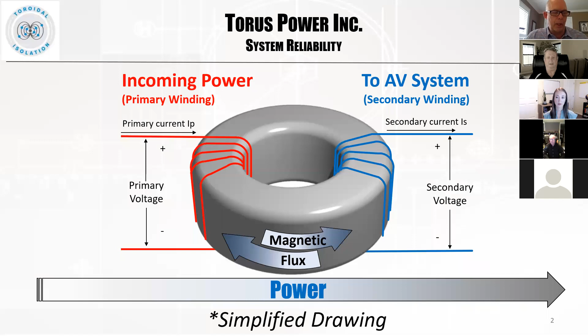So then we'll move on to part 2, which is our automatic voltage regulation. This deals with fluctuations and inconsistencies on the incoming power line—things like surges, spikes, over voltage, under voltages, sags, transients. These are all problems that can occur in the electrical voltage supply that can cause problems or failures in system components. When the power supply in an electronic component that isn't designed for a wide voltage fluctuation is asked to compensate for this, it creates heat that can shorten the life of the component. Regulating the voltage powering the sensitive equipment can solve this problem and add years of life to your components.